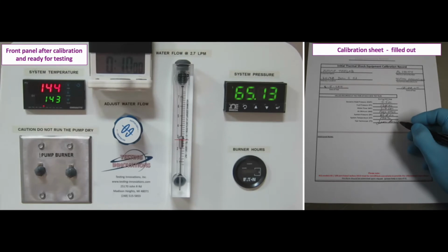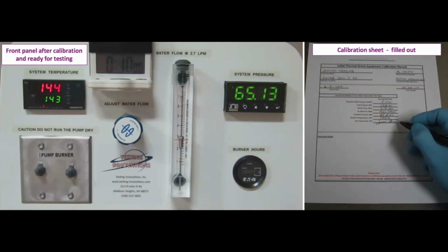Now that you have finished the calibration procedure, let's step back from the picture and take a look at what you have done. You have basically just set the operating conditions that your unit uses to create the 5.5 psi of dynamic head pressure at 2.7 liters per minute of water flow. So once the dynamic head pressure gauge is removed, these operating conditions now become target values that need to be maintained throughout the entire testing session. These target values keep your machine producing the 5.5 psi of dynamic head at 2.7 liters per minute. This is the single most important facet of running a proper test.